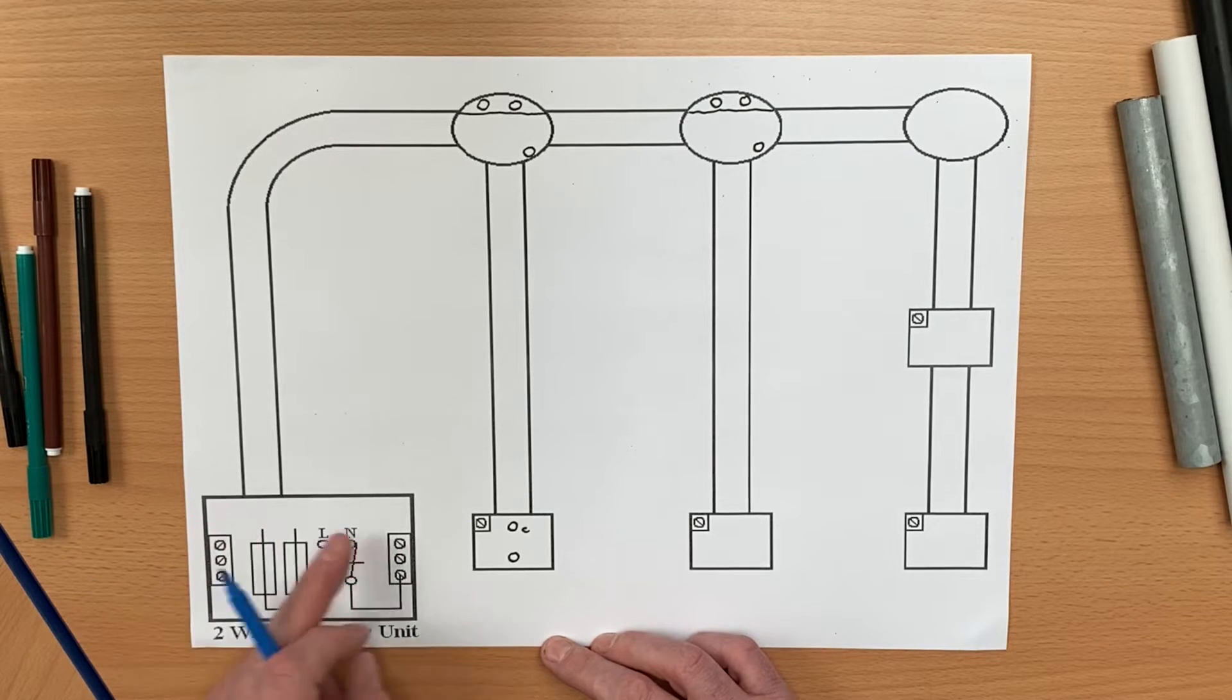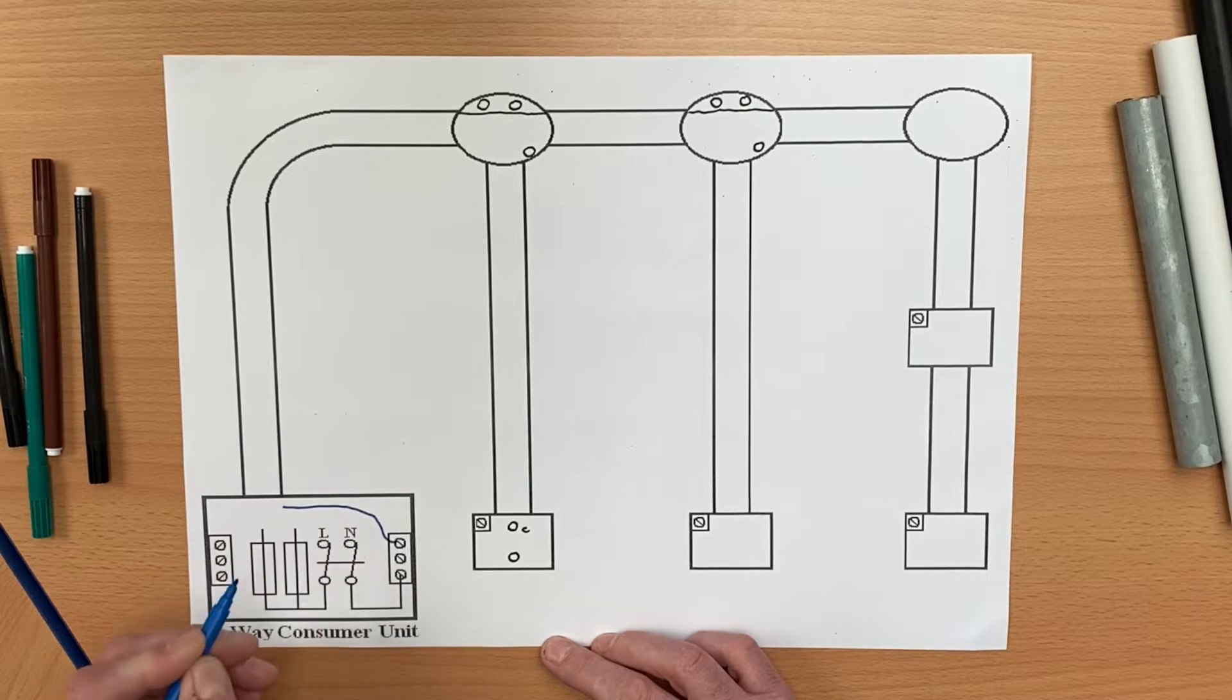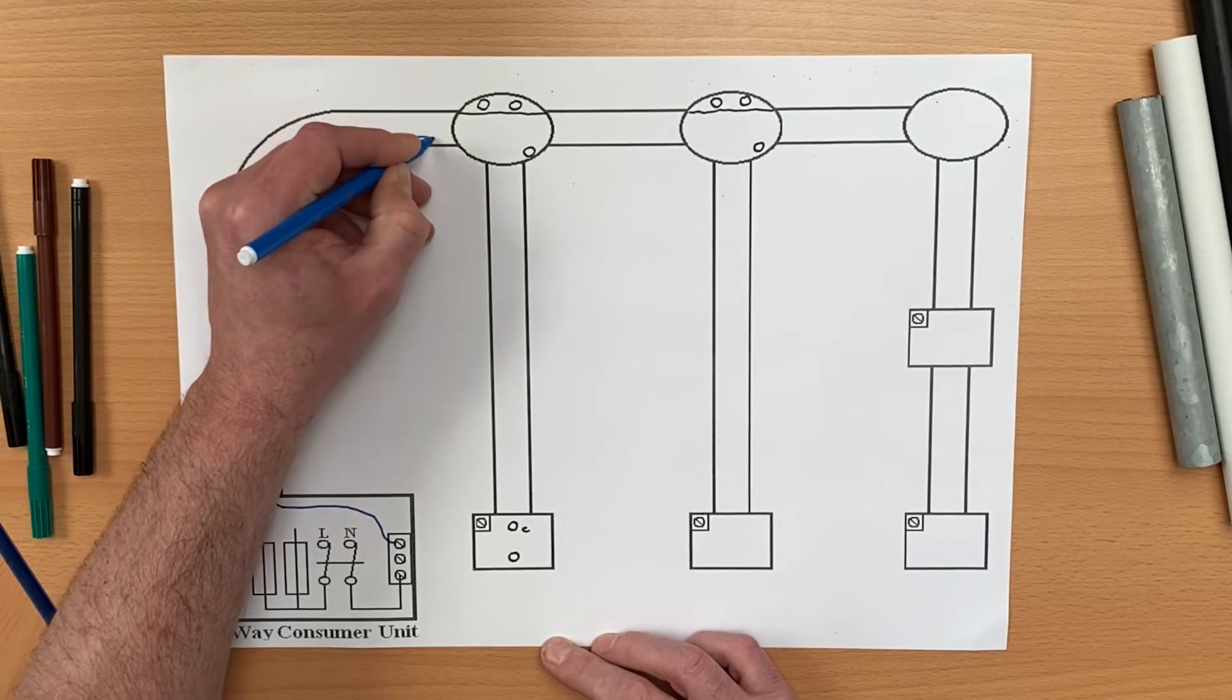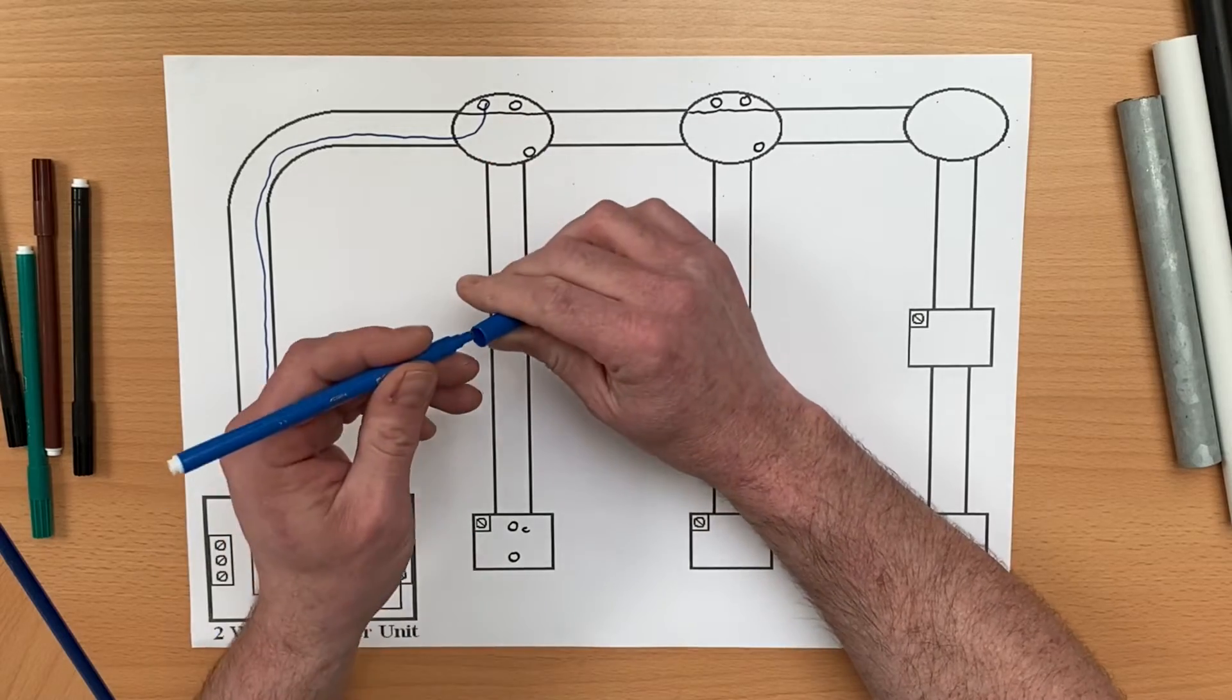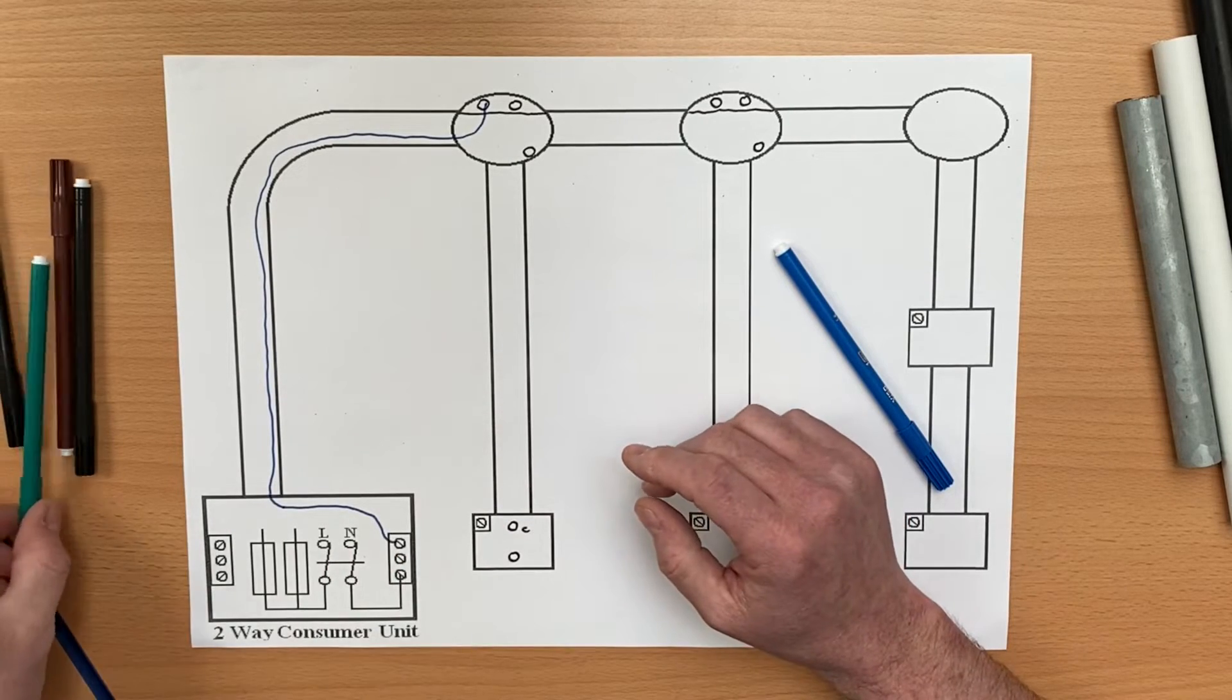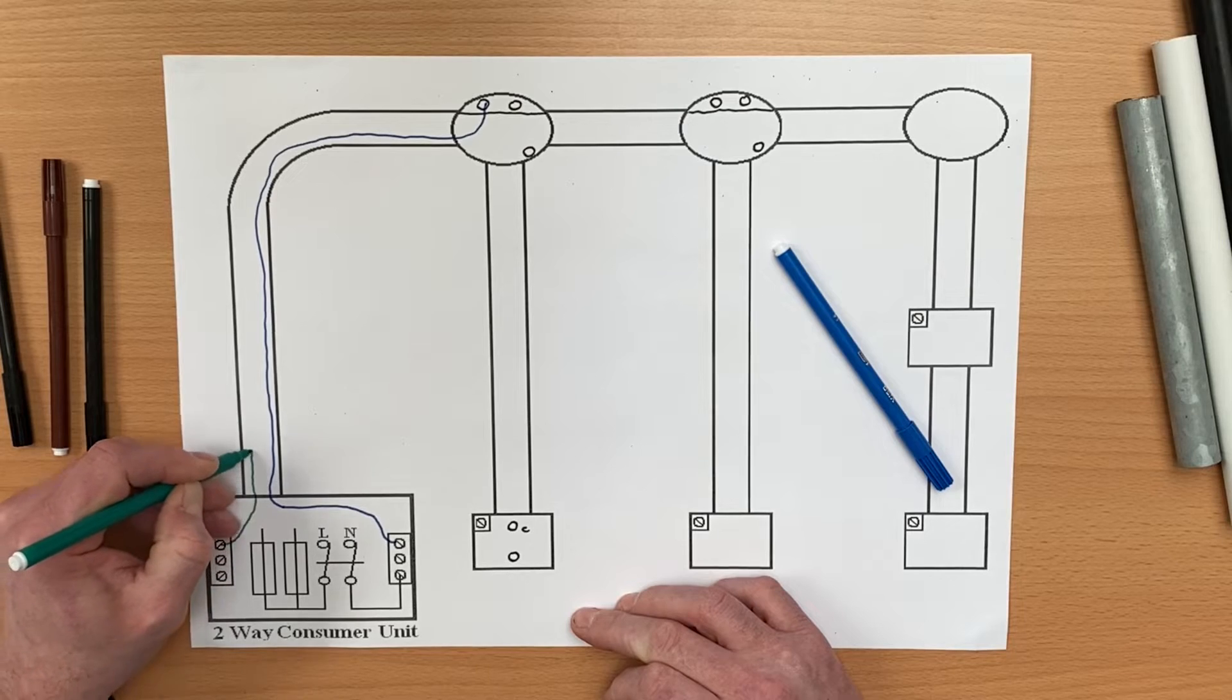Where do we need it? Well we need it up here at our lighting point. So let's bring our neutral—I'm going to use fuseway number 1, CPC and neutral number 1 position, so the earth bar and the neutral bar. Let's take our neutral out from our consumer unit and bring it round and drop it off at our lighting point. Let's leave the neutrals for a minute because we're going to add this light on. Let's just make this one one-way to start with.